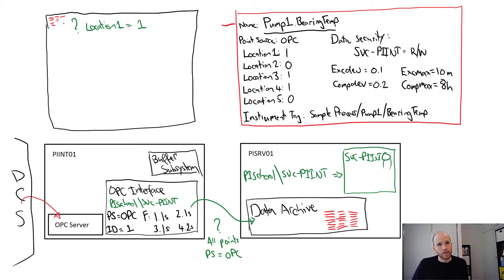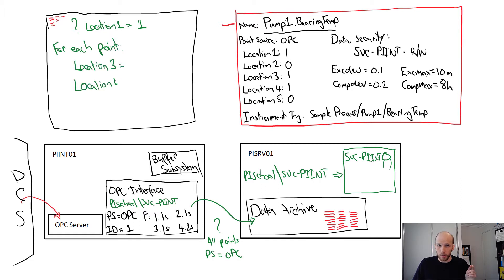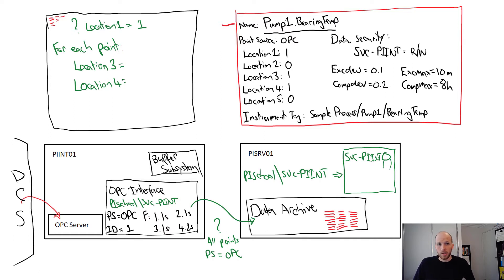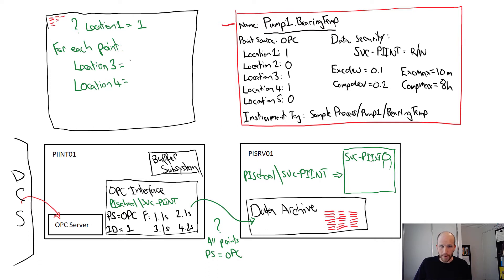Then our OPC interface checks each point in the list's location 3 and location 4. Location 3 controls the processing type of the tag. A 1 would indicate that it's an advise tag, and a 0 indicates it's a poll tag. Our bearing temp tag has a location 3 of 1, indicating it's an advise tag.